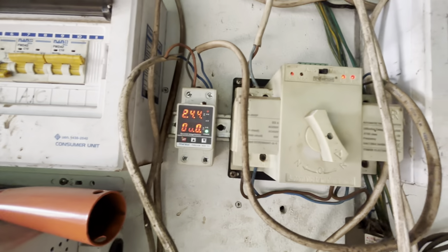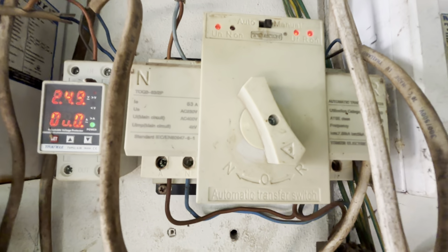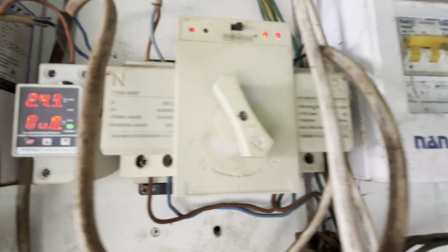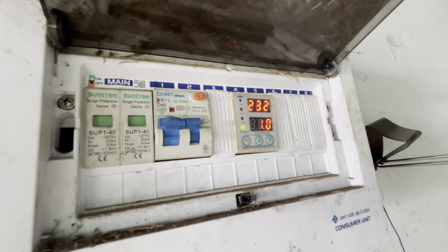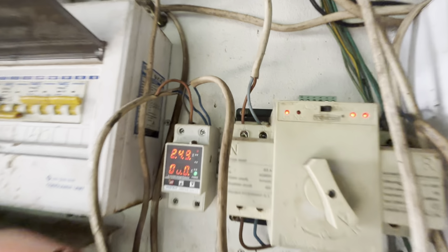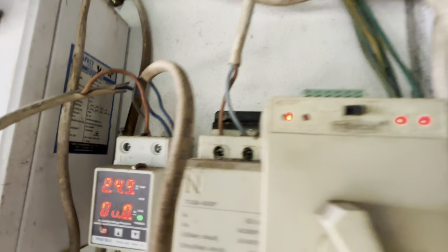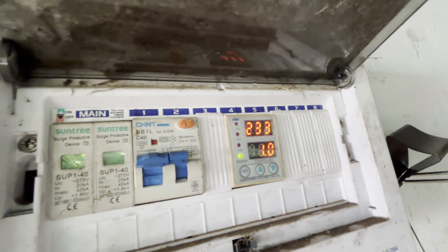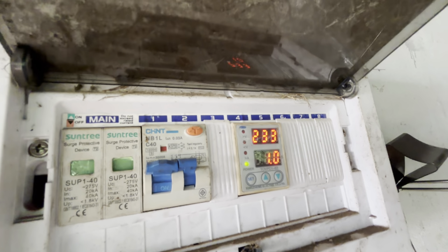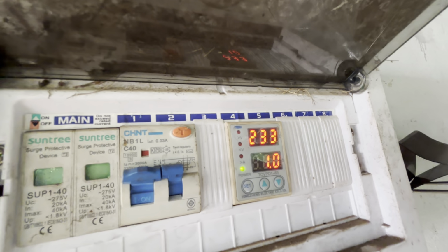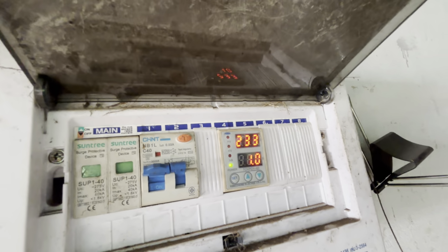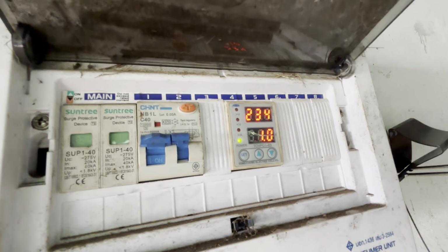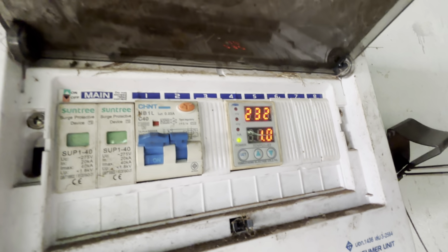So you see that normally when this switch is on reserve, right, it's done it because those two terminals have lost voltage, because that voltage there is lower or has disappeared. Remember, that's normally lower than 200, but I've changed it to 175. So it very rarely now goes, and this is a real outage.